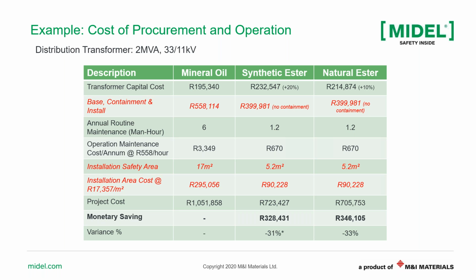Now, almost the final section is the cost, which I will go through briefly. One example is the distribution transformer. Of course, esters, because they offer this K-class, less flammability and biodegradability, cost more than mineral oil, the initial cost of the liquid. And so this can be reflected in the transformer. So for a distribution size transformer, we expect a synthetic ester to be 20% higher cost than a mineral oil one, and a natural ester can be 10% more. This is one example. It depends how you optimize the design.